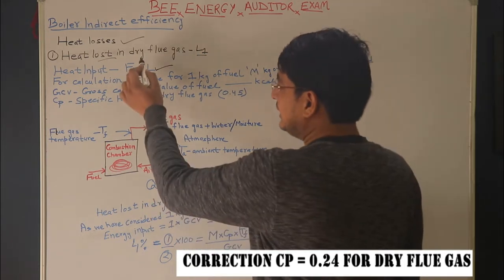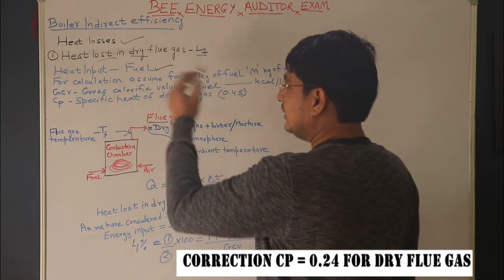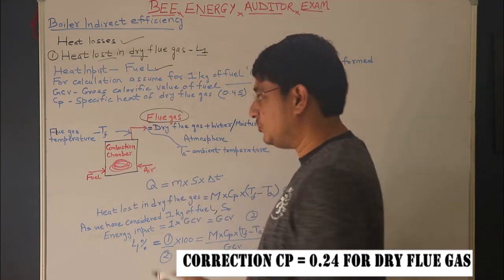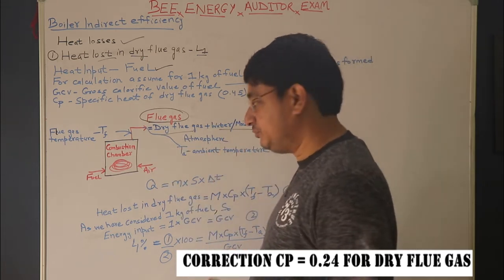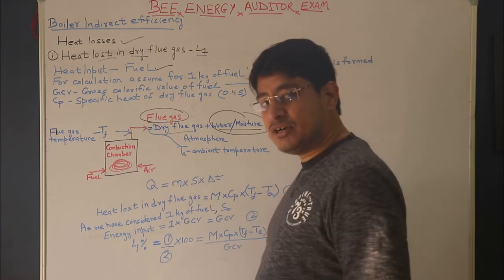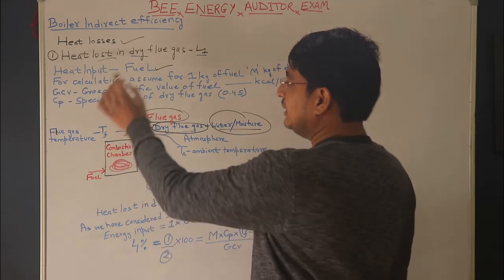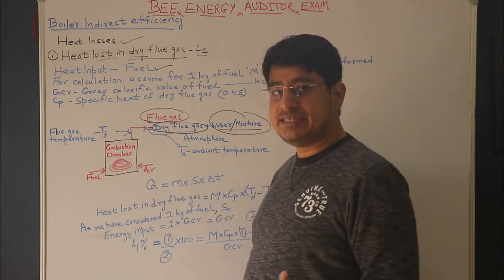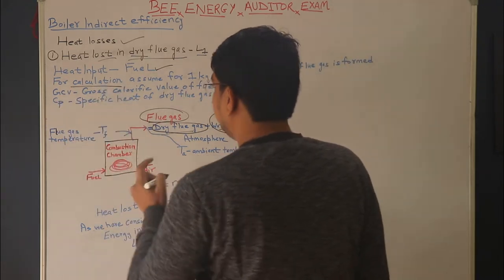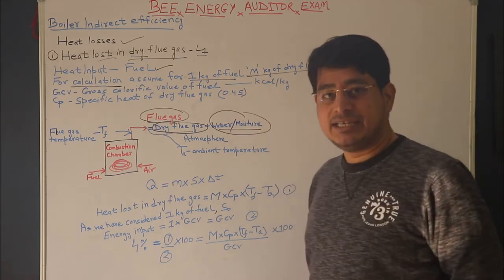For calculation of heat loss in dry flue gas, I consider only the dry part of the flue gas. The flue gas can be broken down into dry flue gas plus water/moisture. The moisture will be dealt with separately. Here I am calculating the loss linked with dry flue gas only. I have assumed 1 kg of fuel, and that m kg of dry flue gas is formed per kg of fuel.